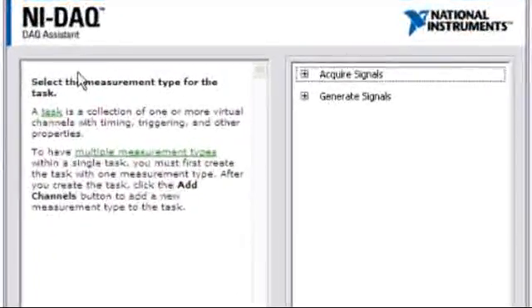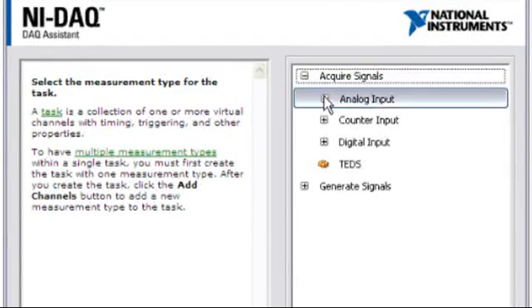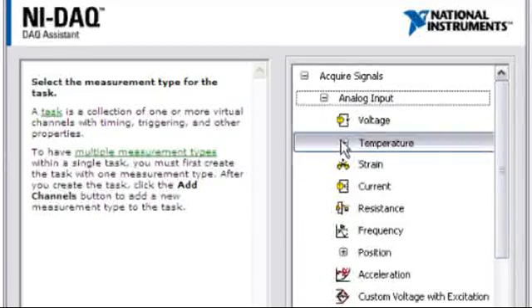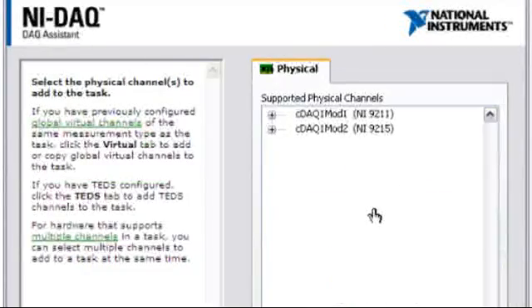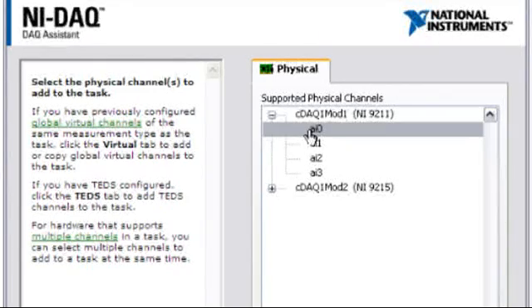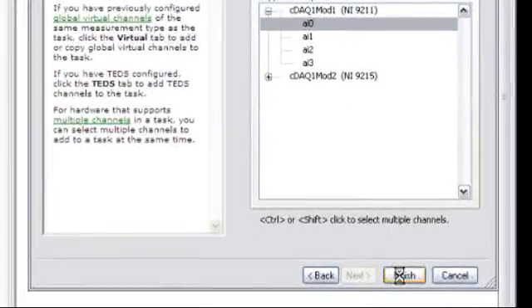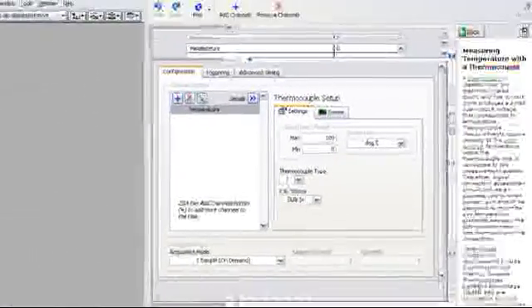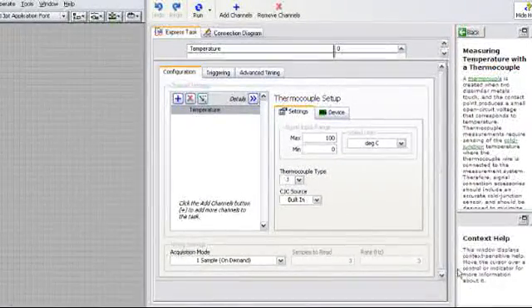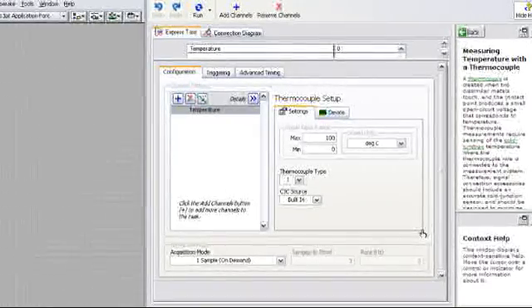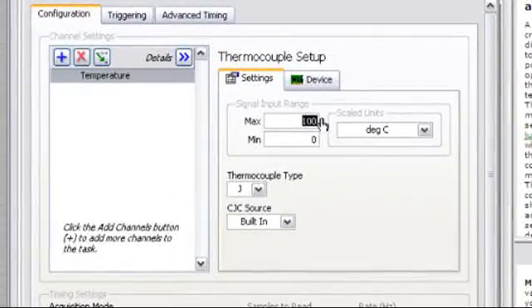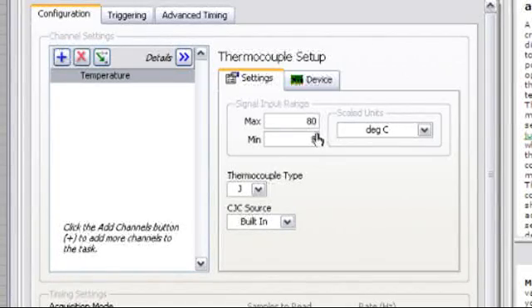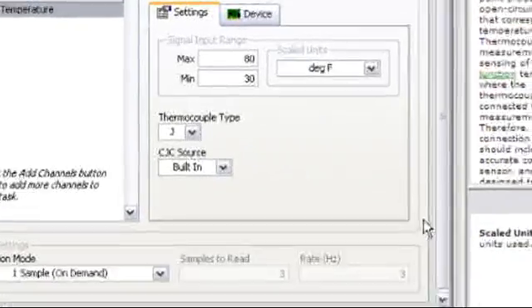And then interact with it through a configuration dialog. In this dialog, I can tell it that I want to acquire an analog signal. I know this measurement is for temperature, and I know that I have a thermocouple. I'm using a 9211 module, and that thermocouple is connected to channel 0. When I press Finish, it brings up a second dialog where I can configure additional settings, such as triggering, advanced timing, or even simple things like min and max temperature. I'll use 80 degrees and 30 degrees as my min and max for degrees Fahrenheit, and then I'll press OK.